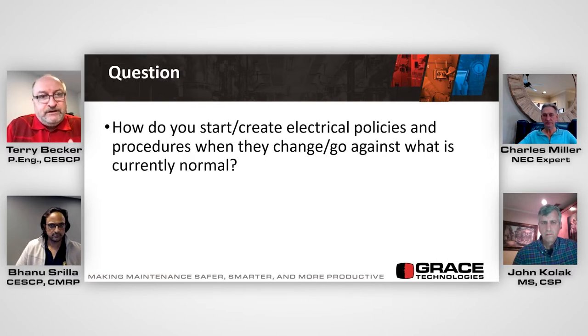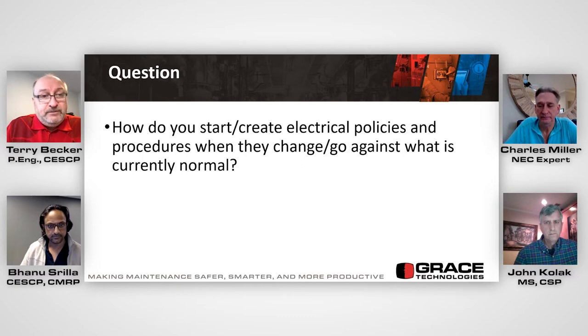So give them a table that covers both arc flash and shock, telling them when they need a permit, when they need a job safety planning form, and advising them of the residual risk level of the work task. We train them on the program, they apply those controls, but the supervisor has to validate that the controls are working. You've got to audit the PPE.